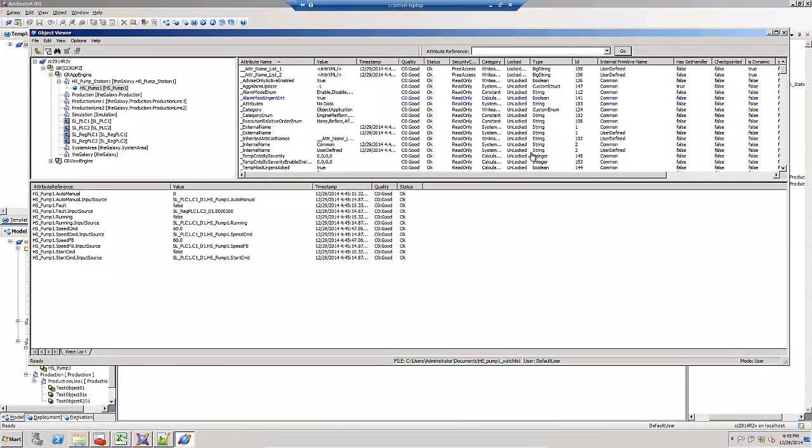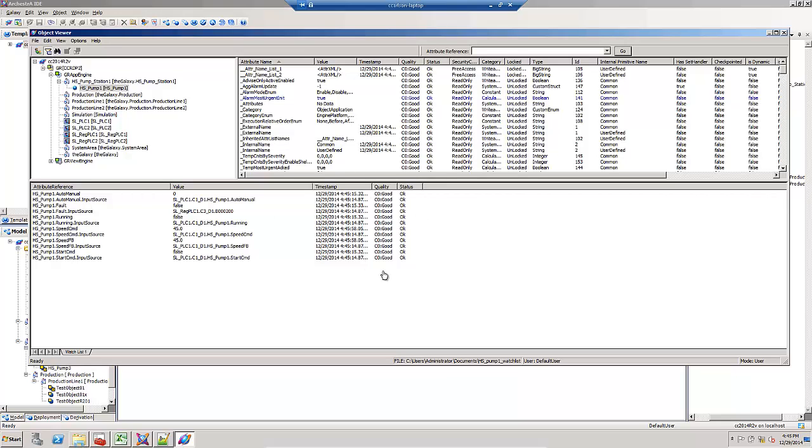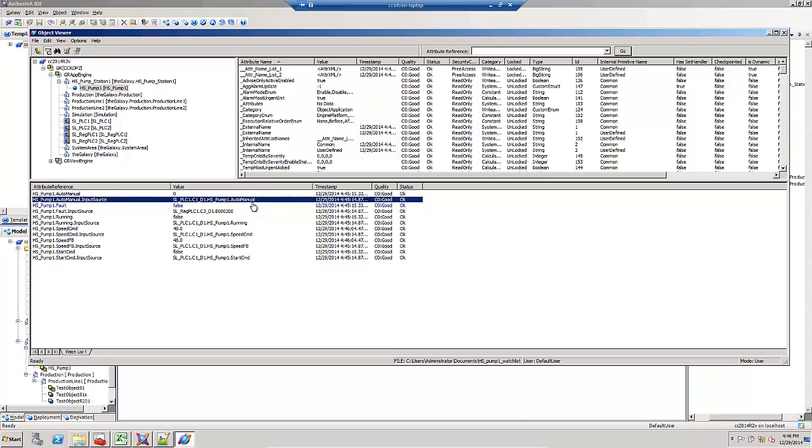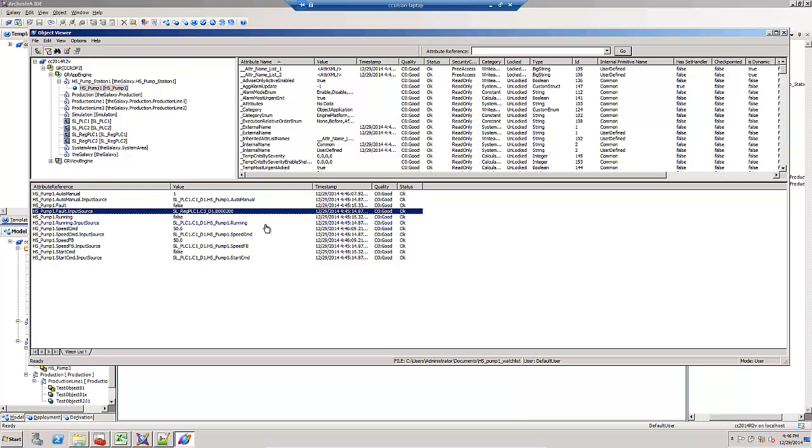Once I've deployed that HS pump one object and look at it in object viewer, I've got each of the attributes shown along with their input source reference. Notice how all the quality and status are good and okay. Here's the reference for one of them that was auto mapped, and here's the one that I've hard coded.